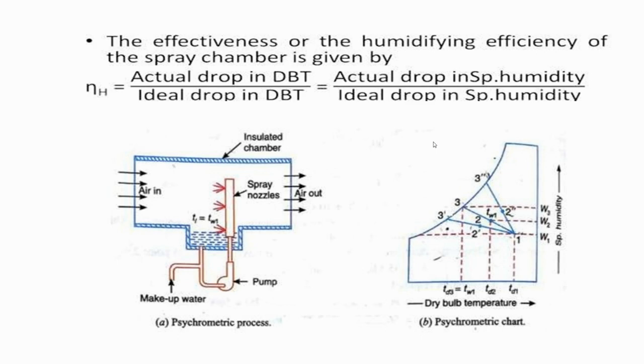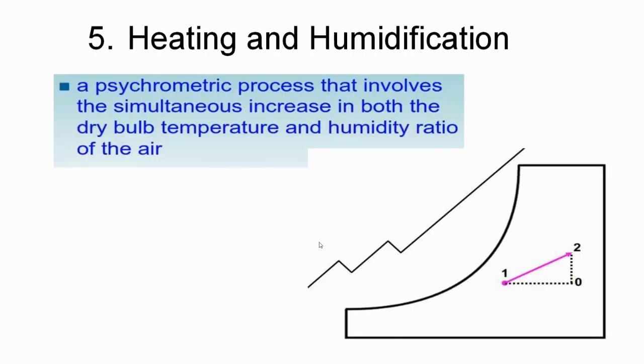The effectiveness or humidifying efficiency of the spray chamber is given by the ratio of actual drop in temperature to ideal drop in temperature, and also equals the ratio of actual drop in specific humidity to ideal drop in specific humidity. This is how we calculate the humidifying efficiency or effectiveness of a coil.